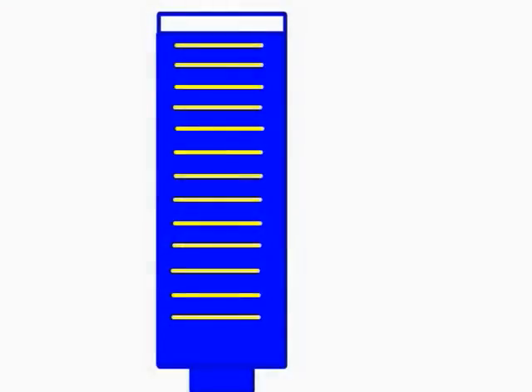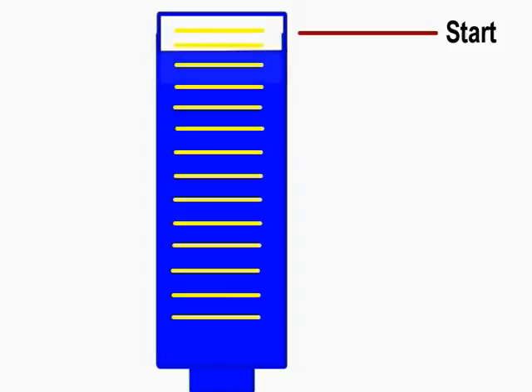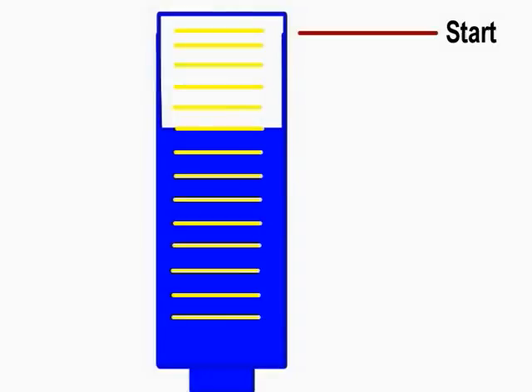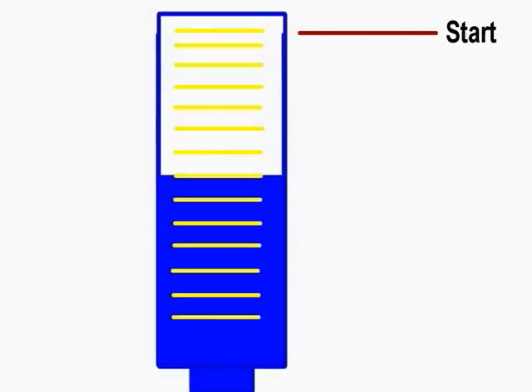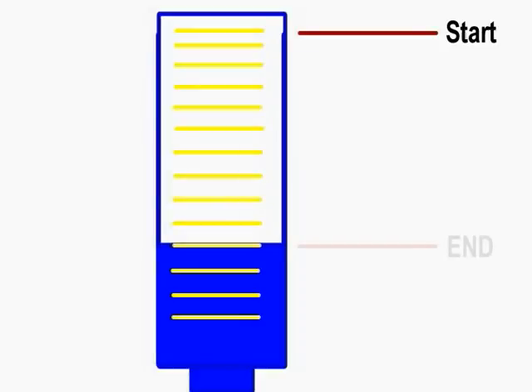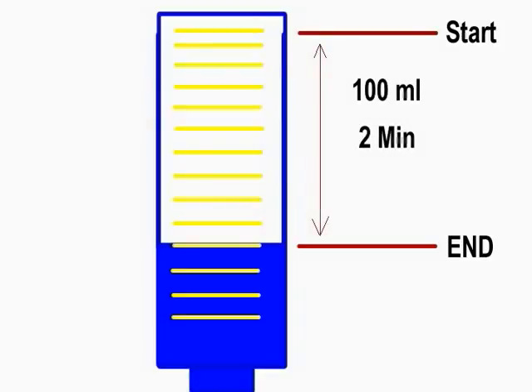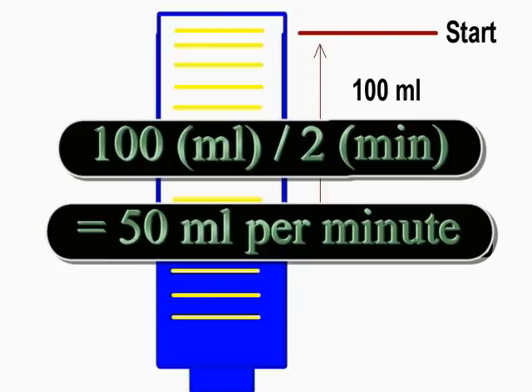Mark the level of the chemical in the calibration tube and start pumping. Time the pump for 2 to 3 minutes. The longer time at the lower stroke settings gives the pump time to become consistent and compensates for any minor glitches the pump may experience. At the end of the designated time, mark the level in the tube and subtract the difference from the starting level. Divide the difference by the number of minutes the test was run for to get the milliliters per minute flow rate.